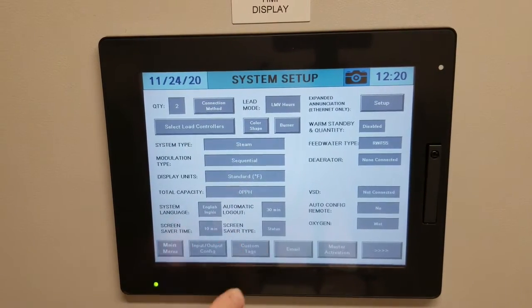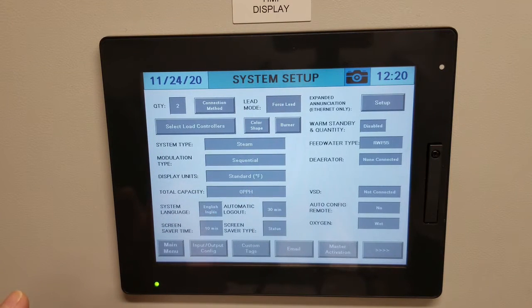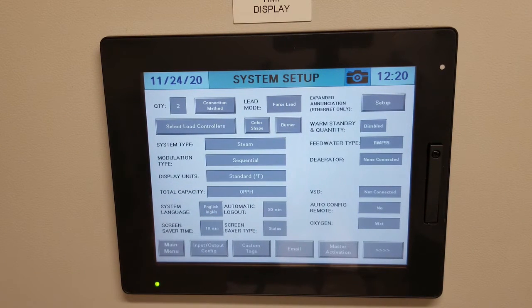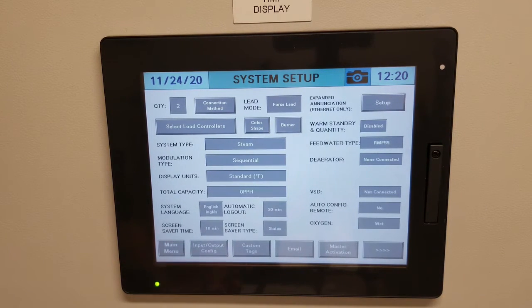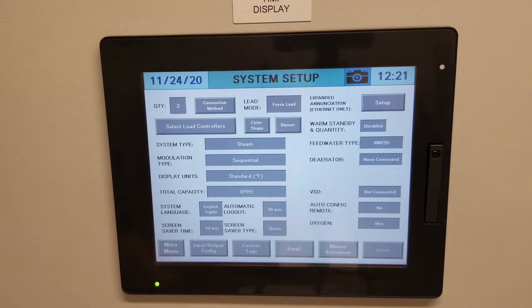Next, what type of lead mode? You have several options. You have LMV Hours, which is based on the run hours of the LMV. You have Forced Lead — one boiler will be the lead boiler at all times and the others will be backup. This works very well in a summer/winter application where a customer may have a small pony boiler for summer operation and two larger boilers for winter. In the summer they want to run the small boiler at all times, but still have the larger boilers as backup in case something fails.